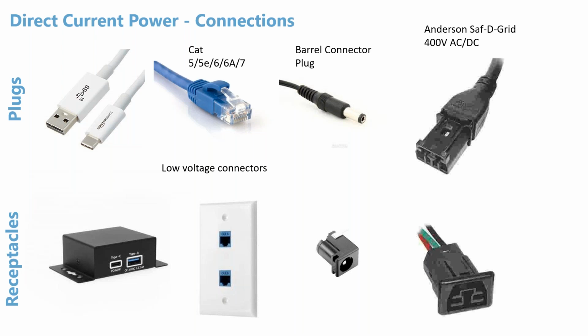Most probably, the industry is going to standardize around a cable similar to this Anderson Saf-D-Grid with the following features. First mate, last break connection, providing the safety of the earthing path before engagement of the power contact. Hot plug rated: the connectors are rated for current interruption for both electronic and electrical loads. Touch safe, which minimizes the risk of personal contact with hazardous voltages, even at this high voltage, 400 volts or 380 volts. It also provides arcing protection: the housing contains the arc if connectors are mated or unmated while under load, minimizing risk to personnel. As for power density, this Anderson Saf-D-Grid can go up to 400 volts AC or DC and up to 30 amps. Next, please.